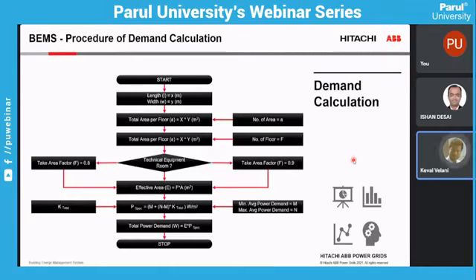Here you can see a typical flow chart procedure of the demand calculation. How do you calculate your demand in a particular building premises? You have to identify the length and width of the building, the total area of the floor, and the power demand per floor. Then check whether technical equipment rooms exist or not, and if they exist, what the calibration factors and demand factors are. According to this building demand calculation procedure, you calculate your demand with reference to different types of application, either residential, commercial or industrial.